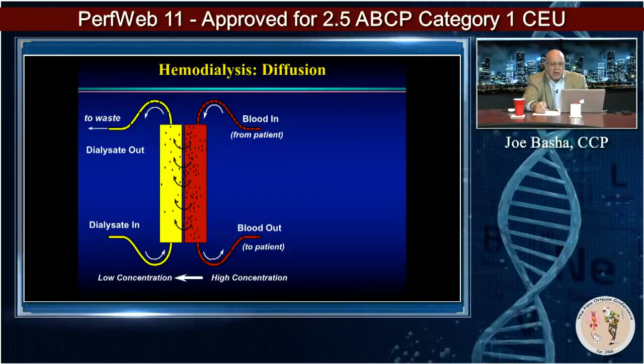But I am going to say that when you do continuous dialysis with a CRRT machine, you will have both diffusive clearance and some level of adsorption. Some of the inflammatory mediators that are too big to cross over will stick to the fiber bundle and eventually clog it up if it's high enough. So it's one of the things you can do when you have a patient in fulminating SIRS—you can put them on a device. You'll frequently have to change the filter if they have a very high inflammatory mediator load. And of course, you're going to do some ultrafiltration with it so you can remove volume as well.